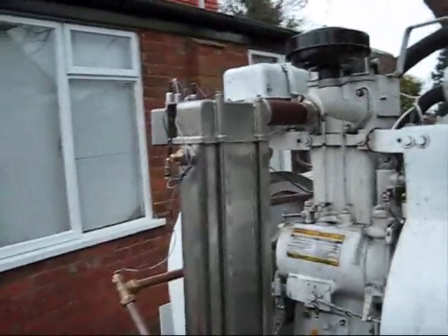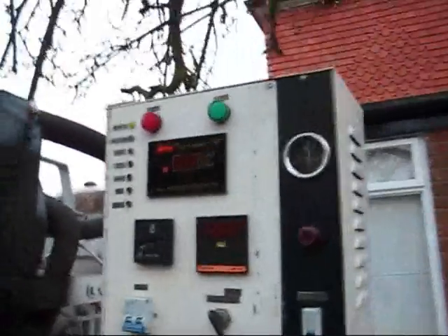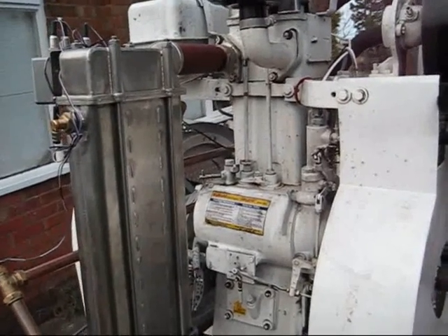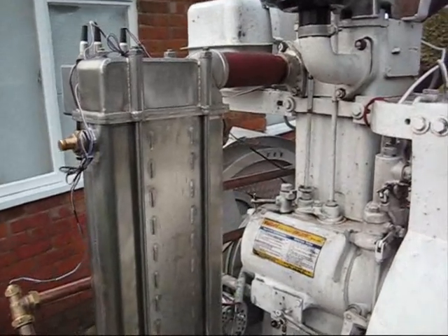This is my combined heat and power system. It is a Lister style generator. The alternator can kick out 6 kilowatts. At the moment it's geared up to run at 650 RPM, which means just a little bit short of 4 kilowatts. It can run between 450 and 1000 RPM.